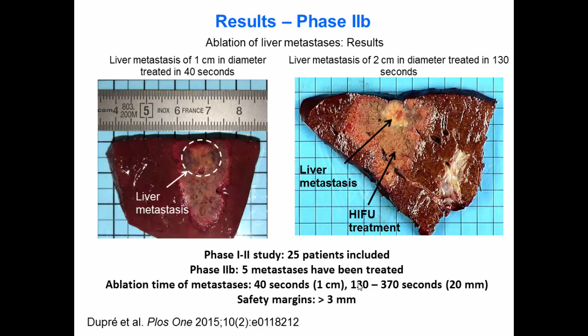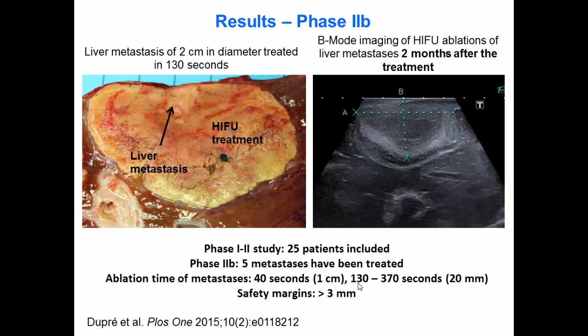So 5 metastases have been treated up to now in phase 2B, and the ablation time varied from 40 seconds for 1 centimeter tumors up to 6 minutes and 10 seconds for 2 centimeter in diameter tumors. And in all cases, we observed safety margins of at least 3 millimeters in all directions. This is another important result. This is another metastasis that has been treated in a patient that was resected 2 months after the HIFU ablation. So this is a 2 centimeter in diameter metastasis that has been ablated using HIFU. And one important finding is that we can still observe the HIFU ablation in sonograms even 2 months after the treatment. So the changes in echogenicity are permanent changes, and it allows us to measure precisely the ablation zone.